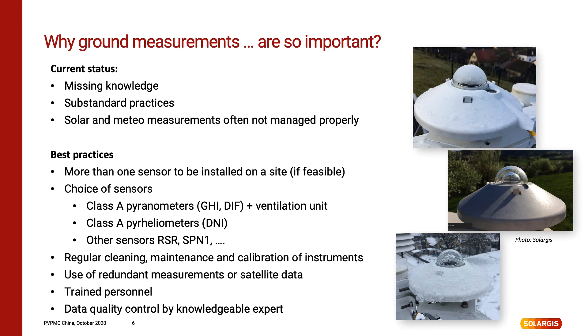If risk of frost, dew or higher dust exists, it is good to use a ventilation unit. For DNI measurements, pyrheliometers are recommended. Other sensors like RSR or SPN1 have higher uncertainty, so they may be used as complementary sensors to main measurements. All this hardware needs regular cleaning and maintenance. Depending on the site, one or two maintenance visits per week is a good standard. Regular calibration is required once per one or two years. All this must be covered by trained personnel.